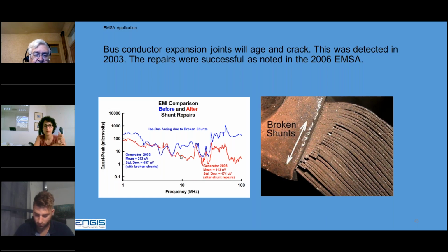2006, we went back. That was the red curve, and it went down. So since the arcing was gone, they knew the maintenance was good. And this whole pattern is low, so there's really nothing wrong with the generator. Only problem was in the broken shunts in the bus.